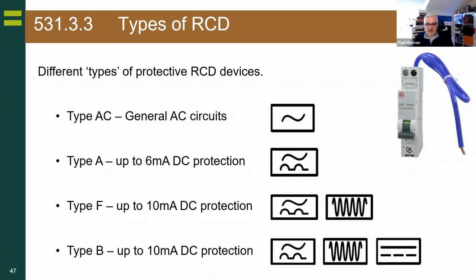Type F has up to 10 milliamp protection for AC and half-wave rectified, and also mixed frequency interference. And then Type B also offers up to 10 milliamp DC protection, and that covers your AC loads, your switch-mode rectified DC, your mixed frequencies, your constant current DC, i.e. battery sources, or your pulsed DC, which can come from control systems which use pulsed DC signals. So it kind of covers everything. Now, in my opinion, and I'm allowed to give an opinion because engineers, we all have them, I can see Type A being the minimum now.